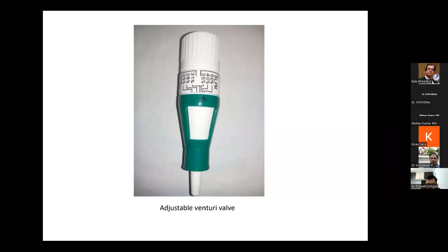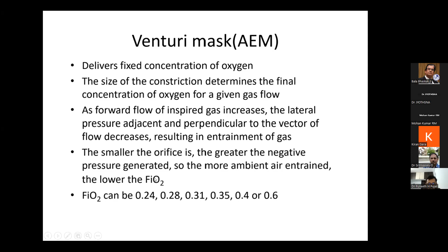This slide will explain the principle of the Venturi mask. It delivers a fixed concentration of oxygen. The size of the constriction determines the final concentration of oxygen for a given flow. I'll explain the constriction in the next slide. As the forward flow of inspired gas increases, the lateral pressure adjacent and perpendicular to the vector of flow decreases, resulting in entrainment of gas. These lines are very important. The smaller the orifice, the greater the negative pressure generated, so the more ambient air is entrained and the lower the FiO2.